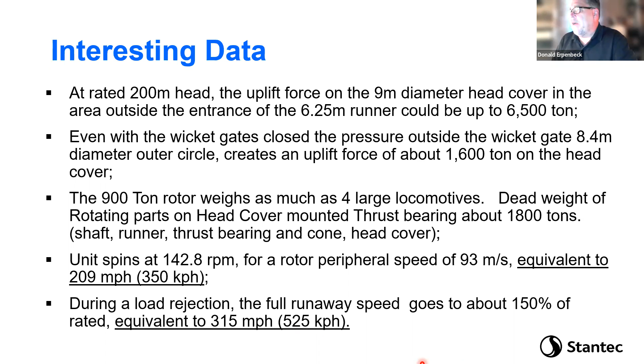All right. So fundamental root cause was this unit had a lot of unusual vibration. They ran it in a rough zone and did things they shouldn't have been doing with this machine. Of the 80 head cover bolts, 41 had fatigue fractures. And 6 of them had no nuts on them at all. 6 of them weren't even bolted down. They don't know why. They theorized that the people doing the engineering investigation were going to be mounting something on them, maybe some type of instrumentation on those 6 the next day, but none of those people lived to tell exactly what they were seeing. But there is no doubt that the failure was fundamentally a fatigue failure of these stationary bolts.